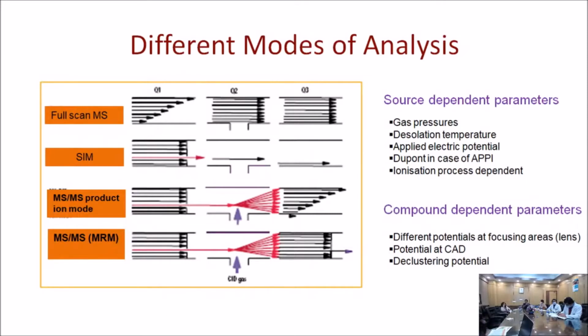Two major types of experiments are done here. For quantitative analysis, there's single ion monitoring, where you select only the ion of interest. Suppose I'm looking for cortisol inside the blood—I will allow only cortisol to be separated in quadrupole 1, quadrupole 2, and quadrupole 3, in case I'm not going for fragmentation at all. Here you get a very high degree of sensitivity, but when it comes to selectivity, it is compromised.